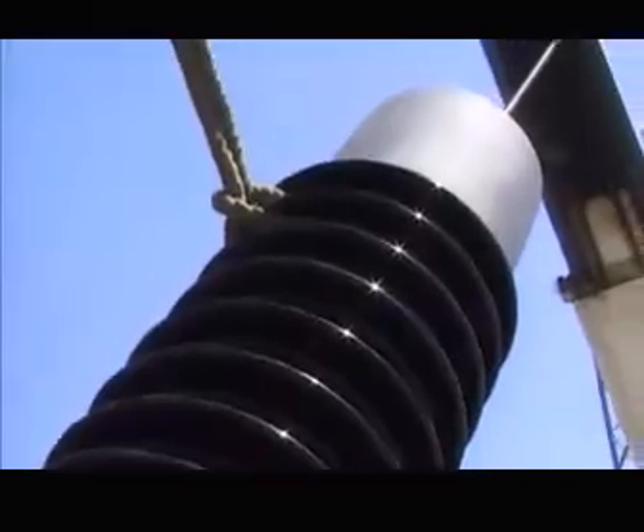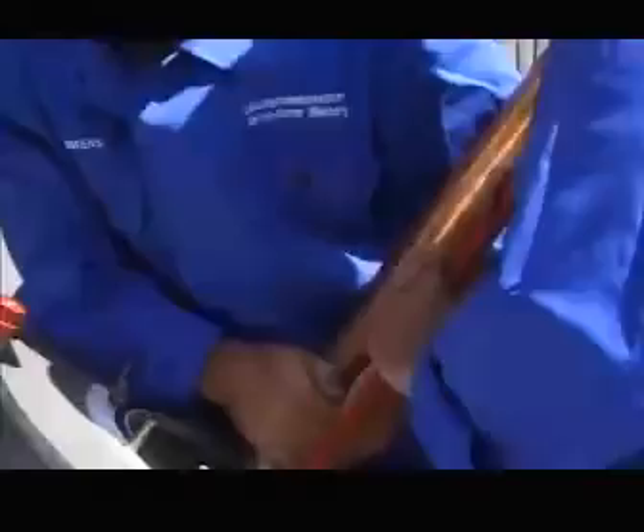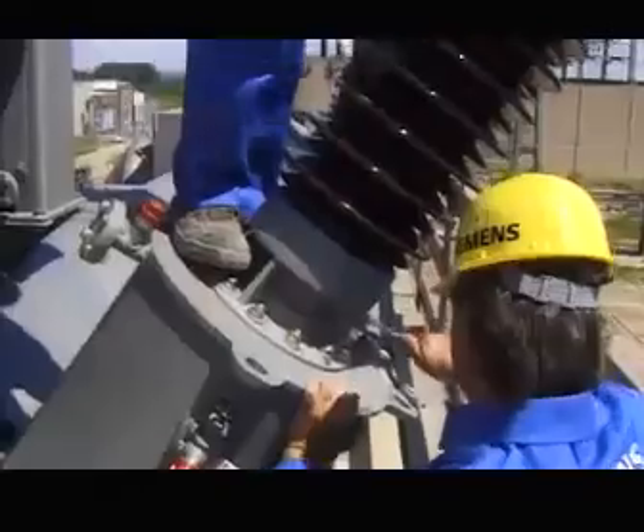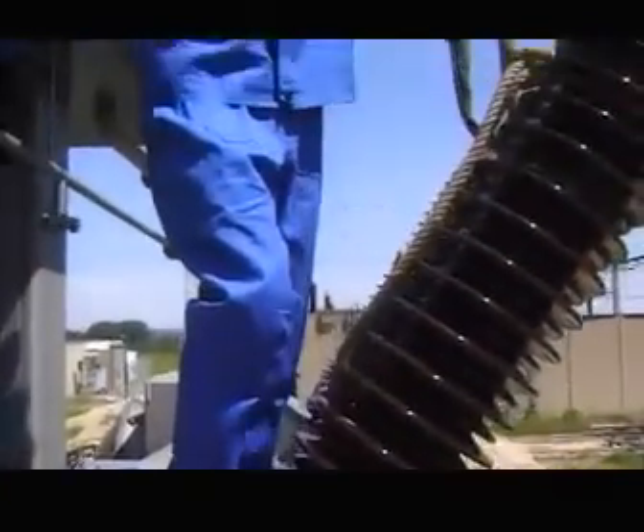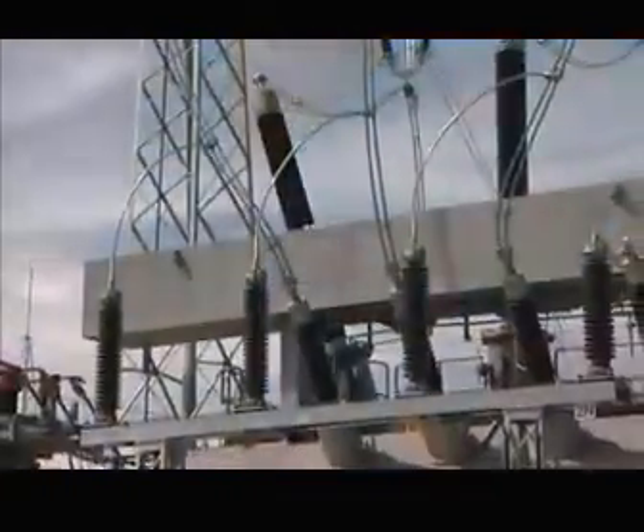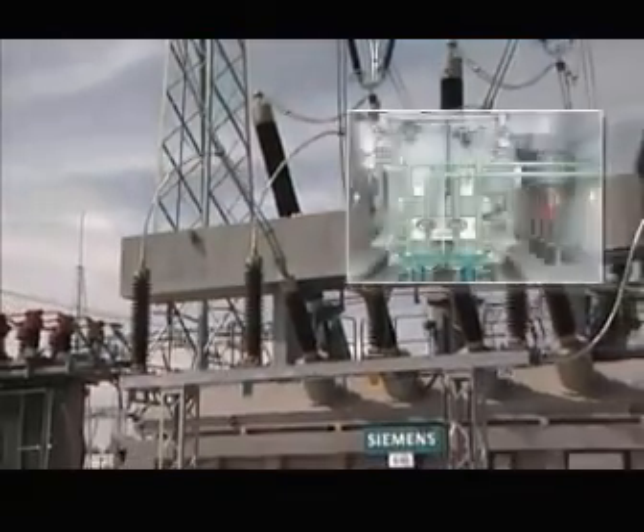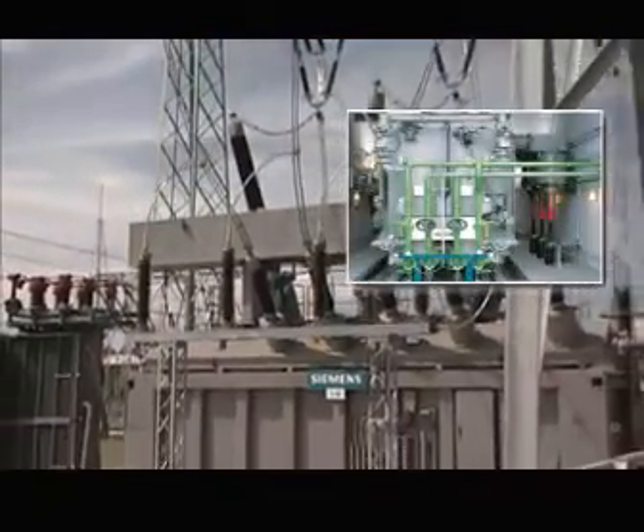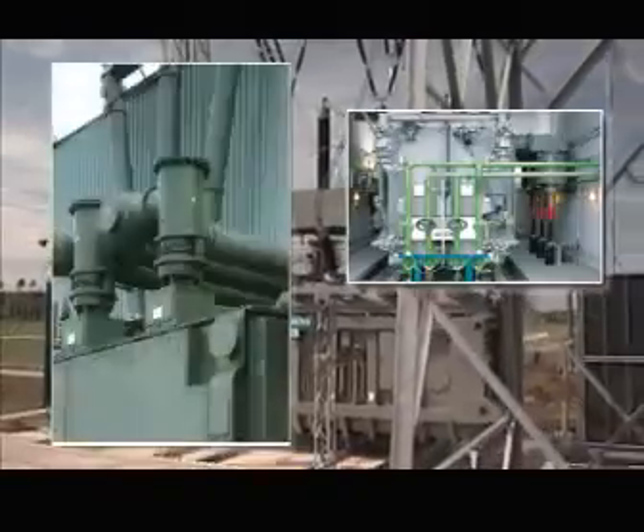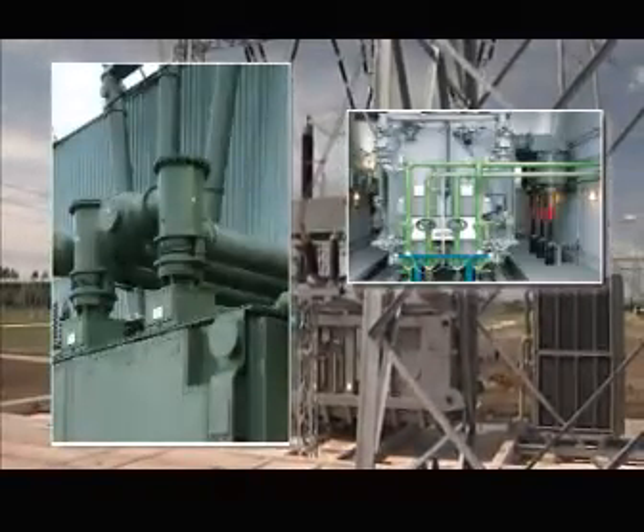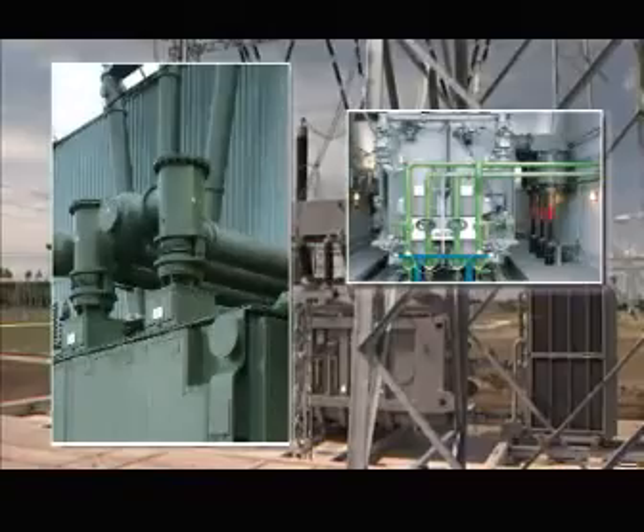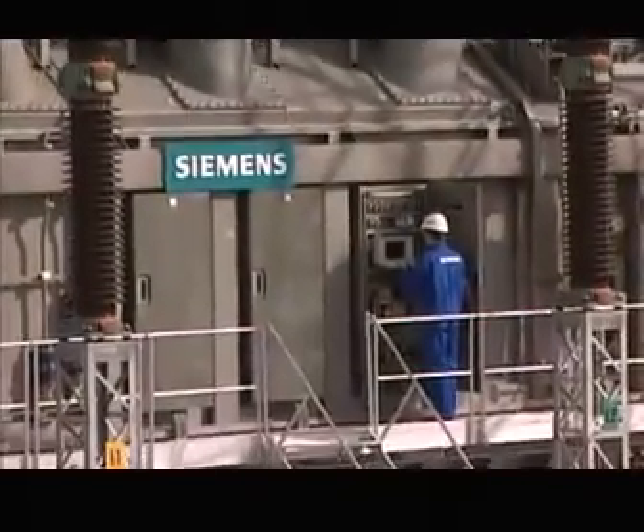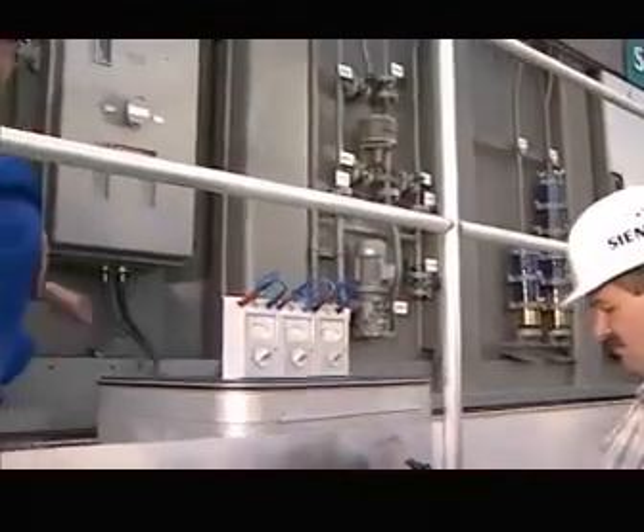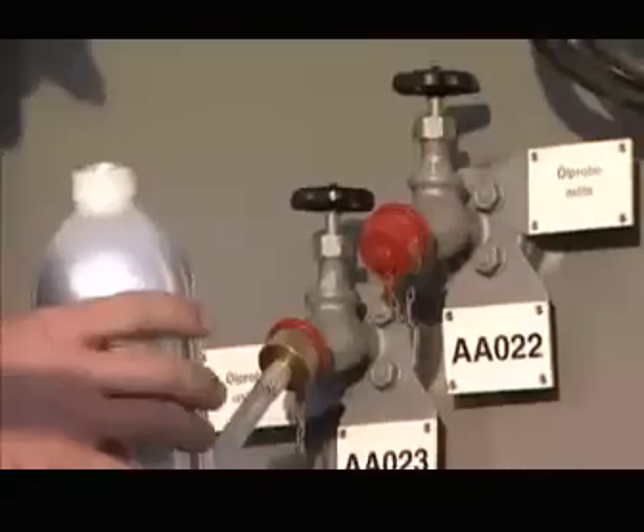The connection techniques used depend on local conditions. The most frequently used method is open-air connections. If space is at a premium, a cable connection is the most suitable. For high-voltage transformers in built-up areas, we prefer a direct SF6 encapsulated connection. We guarantee our customers trouble-free operation for many decades and around-the-clock maintenance service.